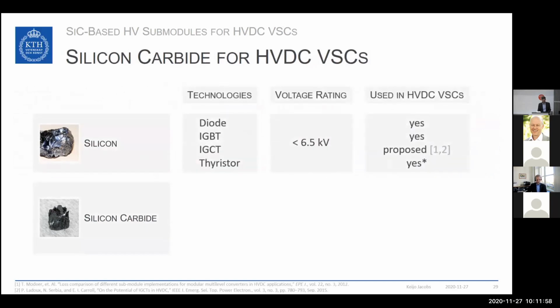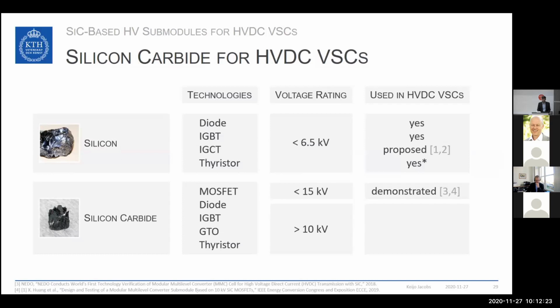The silicon devices used in the high voltage sector are diodes, IGBTs, IGCTs, and thyristors. Those usually have a voltage rating of lower than 6.5 kilovolts. And in HVDC VSCs, we use diodes, IGBTs, and thyristors for bypass equipment. The use of IGCTs has been proposed. For silicon carbide, however, the possible devices are MOSFETs, diodes, IGBTs, GTOs, and thyristors. MOSFETs can have, or are foreseen to have, a blocking voltage of up to 15 kV, and demonstrations for such an implementation have been made. However, for the bipolar silicon carbide devices, such as diodes, IGBTs, GTOs, and thyristors, which have a blocking voltage higher than 10 kV, no demonstration has been shown yet.